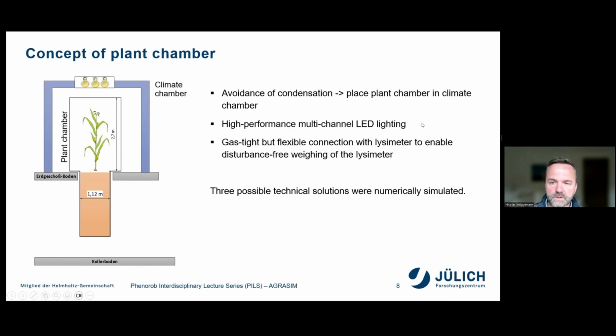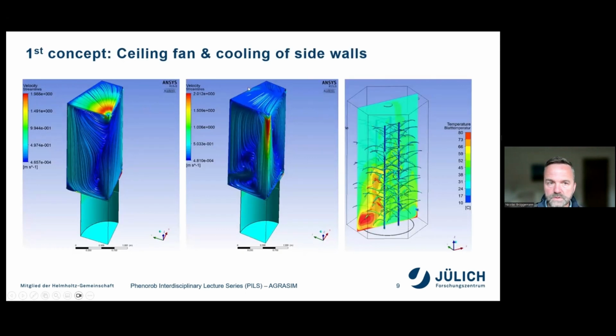Then we wanted to have a high-performance multi-channel LED lighting system and a gas-tight connection to the lysimeters, but that will not disturb the weighing of the lysimeters. That was also the challenge. So we then tested 3 possible technical solutions for the cooling concept of the plant chamber. The first concept was a ceiling fan. This was only numerically simulated by our colleagues from the Central Engineering Department of Forschungszentrum Jülich. The first concept had a ceiling fan and the cooling of the side walls, but the resulting temperature distribution showed that we would have got a very heterogeneous temperature distribution with too high temperatures in some parts of the chamber, because the cooling capacity of this concept was not sufficient.